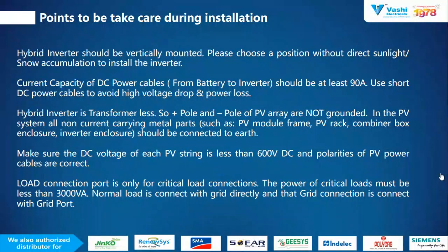The hybrid inverter is transformerless, so the positive and negative pole of the PV array should not be grounded. But you can connect the earthing of the PV module frame, PV rack, DCDB portion or inverter enclosure to the earthing. Means you can connect other devices like the PV rack system, DCDB part, PV module frame or inverter enclosure to the earthing, but you can't directly connect the negative or positive pole of the inverter to the ground. Otherwise, it will give the fault indication.